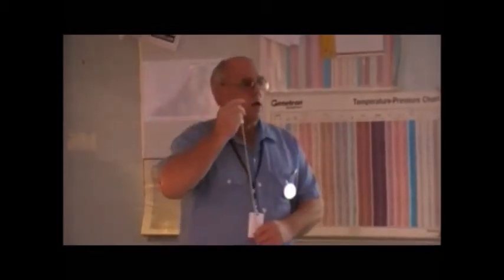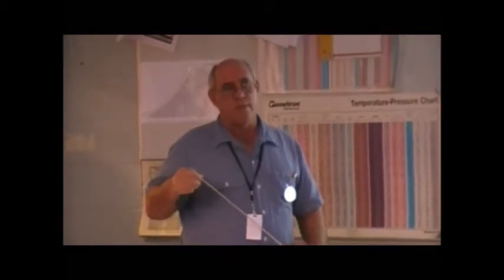And while I'm thinking on this, in homes, a lot of times people will say, well, you know, I've got a lot of trees around my home and it's really shaded. Do I really need that big of a unit because I'm going to have that shade? I don't know about where you're at, but we do have severe weather to come through from time to time in our area. And those beautiful trees may not be there tomorrow after a storm comes through. And you know, a tree doesn't grow up overnight. So I would never, ever, ever use the vegetation, the exterior vegetation, to decrease my loads for cooling. That's just, like I said, that's some lessons I've seen. I wouldn't say that I ever did it, but you know. Good advice, David. Great advice. All right, we're going to be moving on into the doors in just a minute, but that gets our glass.